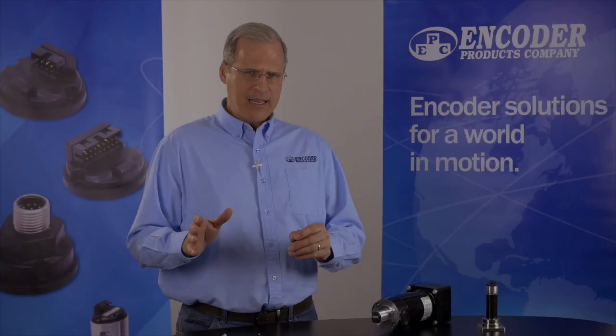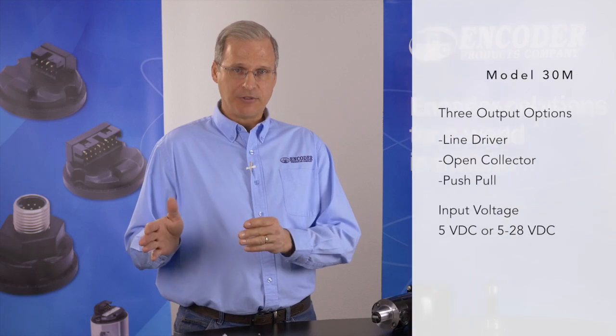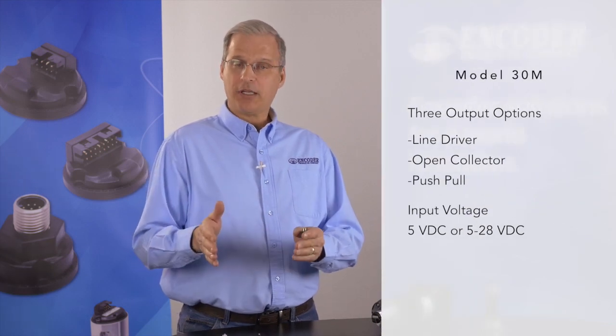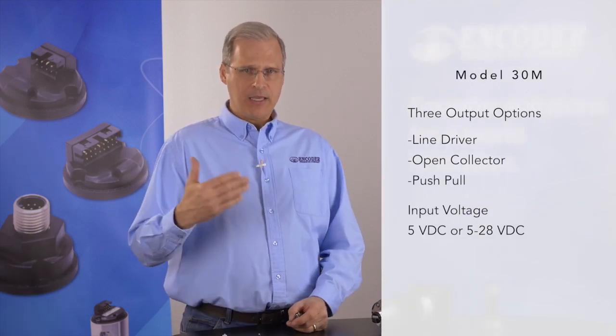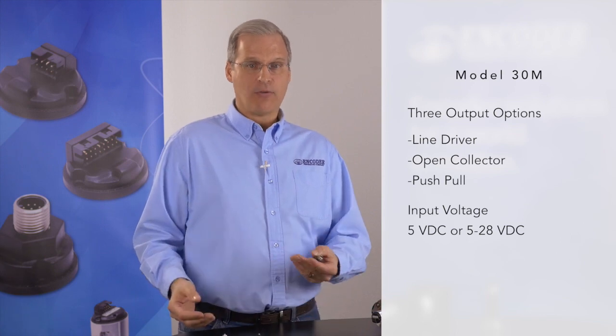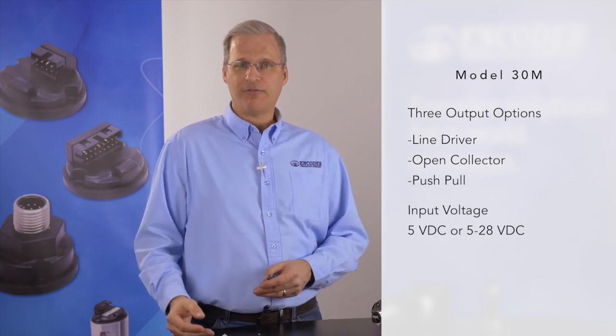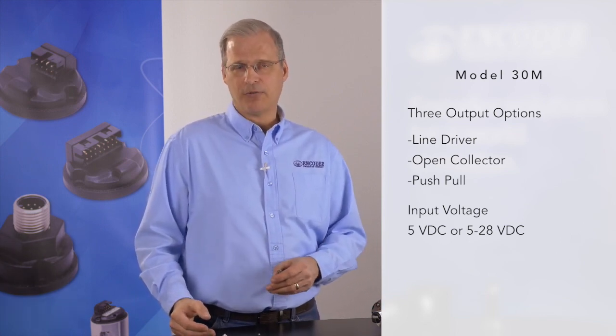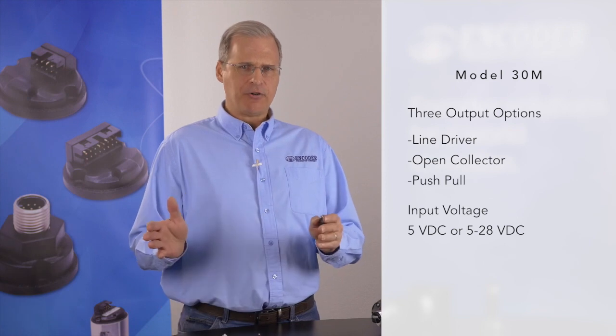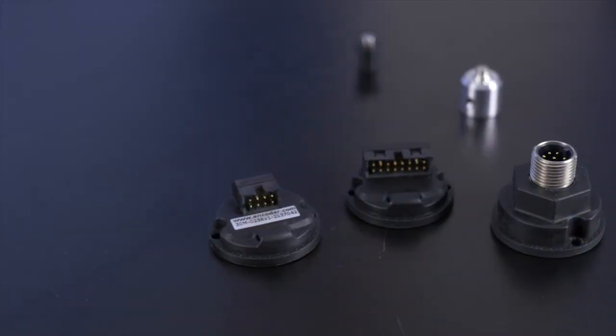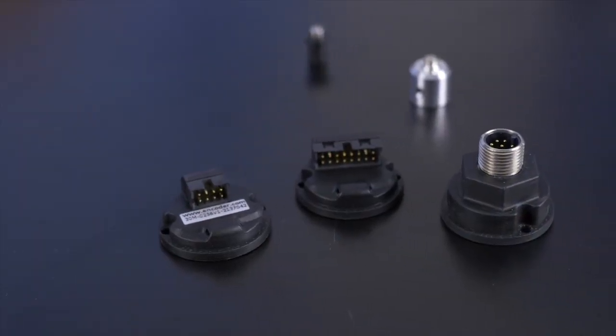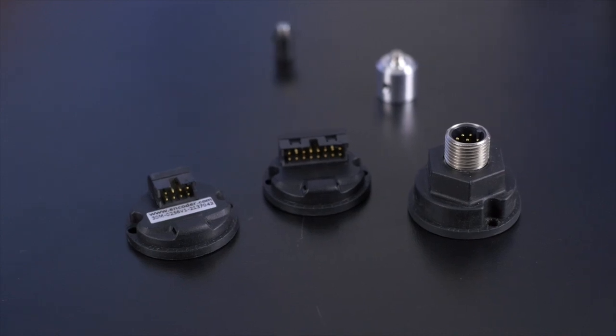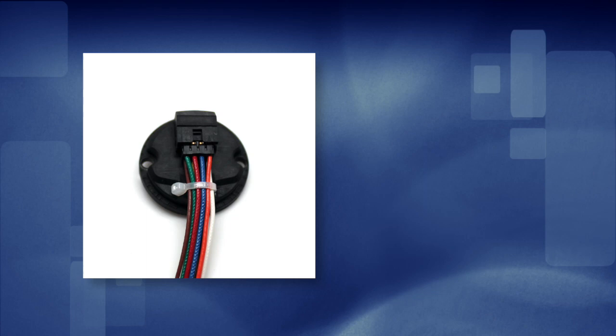There are three output options: high voltage differential line driver, open collector or push-pull. Input voltage is either a fixed 5 volts DC or a variable voltage of 5 to 28 volts DC. You have your choice of an 8-pin or 16-pin Molex-style connector or an 8-pin M12 threaded connector. And there's even a built-in cable strain relief to which you can apply a zip tie, for example.